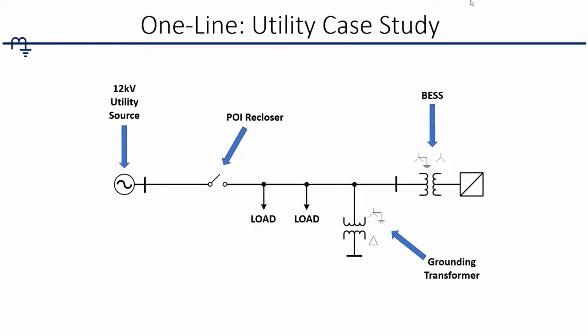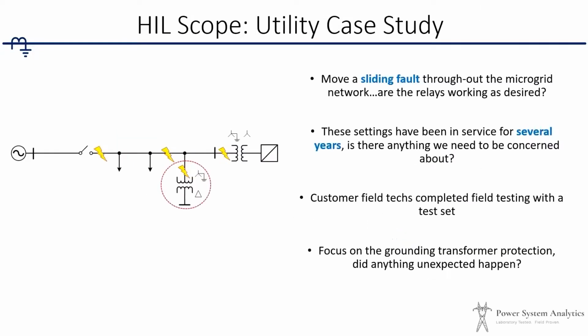So here's a simplified one line of the system we were working on, and I boiled it down to a simplified system. It was a 12 kV network. You had a point of interconnect recloser that tied back to the utility system. You had some pretty simple loads, and there was a battery energy storage system on the network that was part of the microgrid, and it had a grounding transformer that was a Y grounded delta. This utility had chosen that over a zigzag transformer for various reasons, but the BESS unit was around 5 megawatts, I believe.